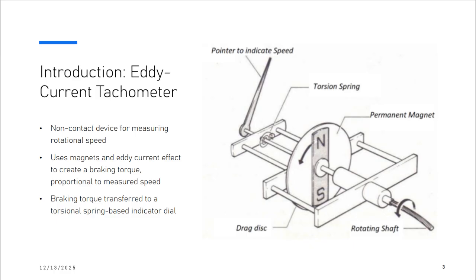I'm going to give a brief overview of how the eddy currents work in our eddy current tachometer. First, we have a permanent magnet that's connected directly to a shaft. As that shaft rotates, the magnet spins along with it, creating a constantly changing magnetic field in its vicinity. Positioned very closely to the spinning magnet is a non-magnetic but electrically conductive disc made of aluminum. This disc is not directly connected to the rotating shaft. Instead, it is attached to a spindle that is restrained by a spiral spring and connected to our indicator pointer.